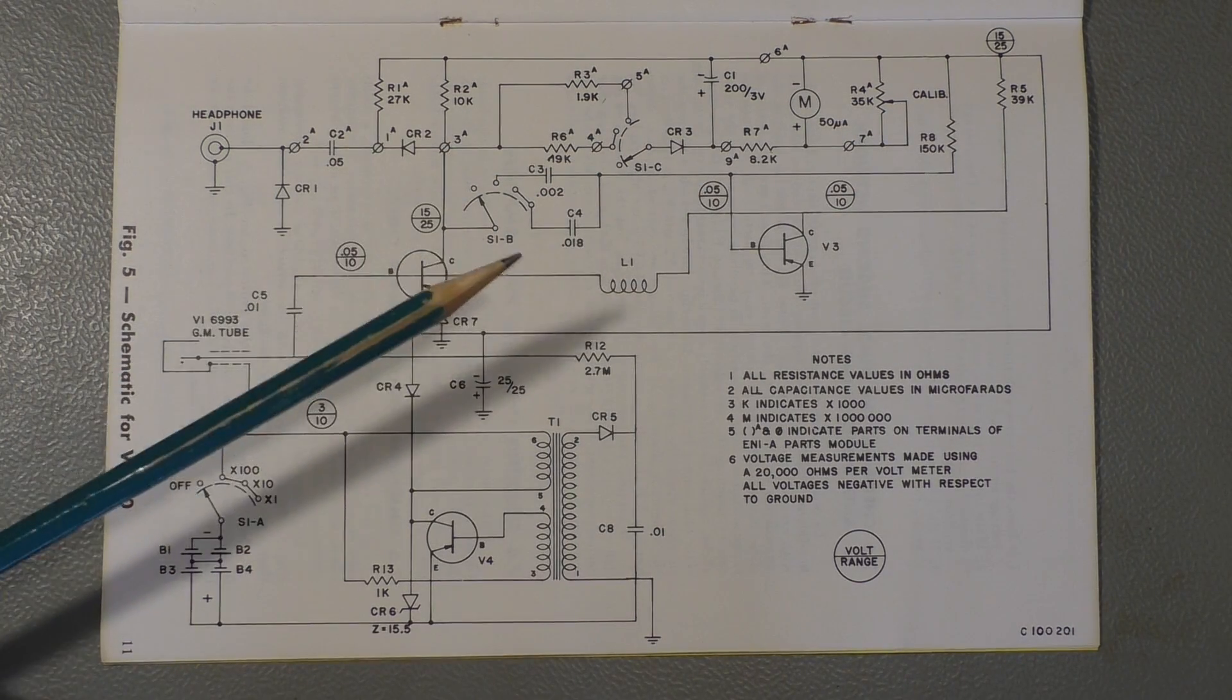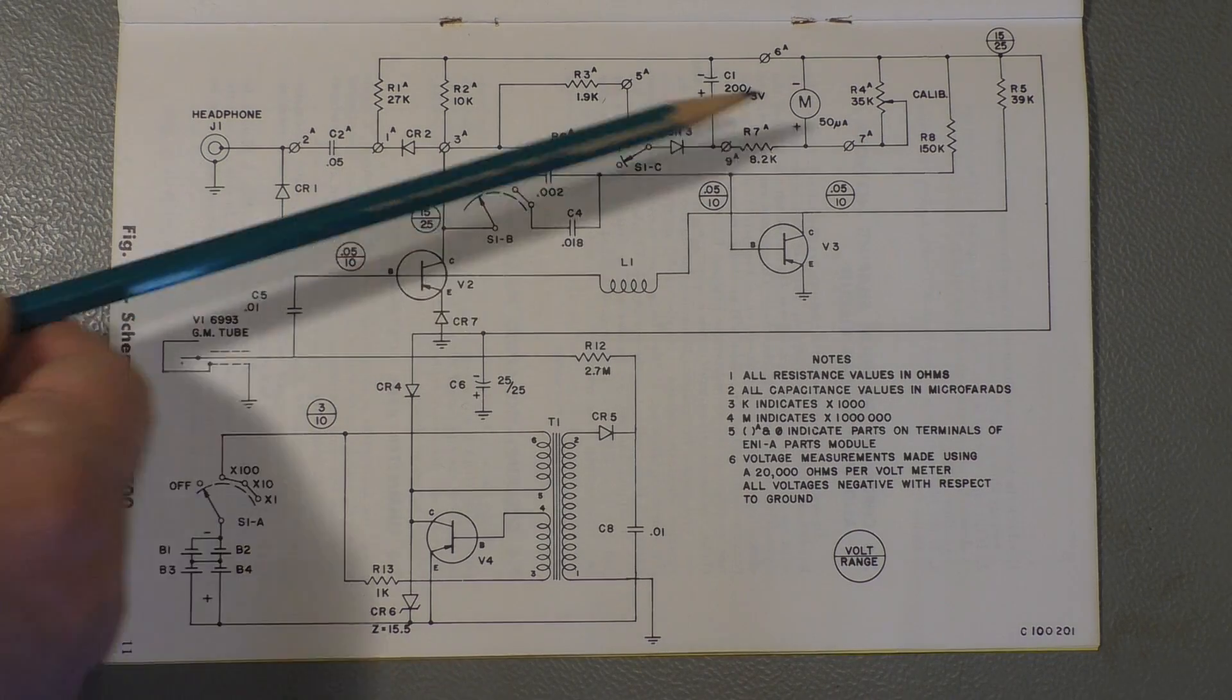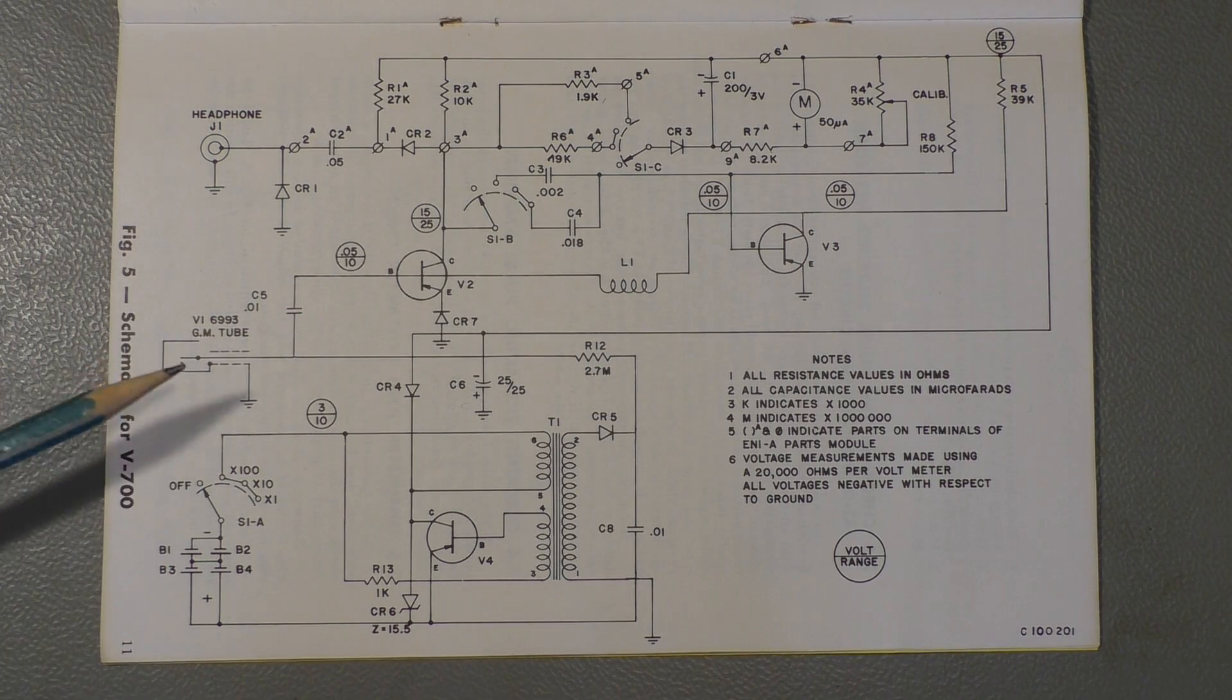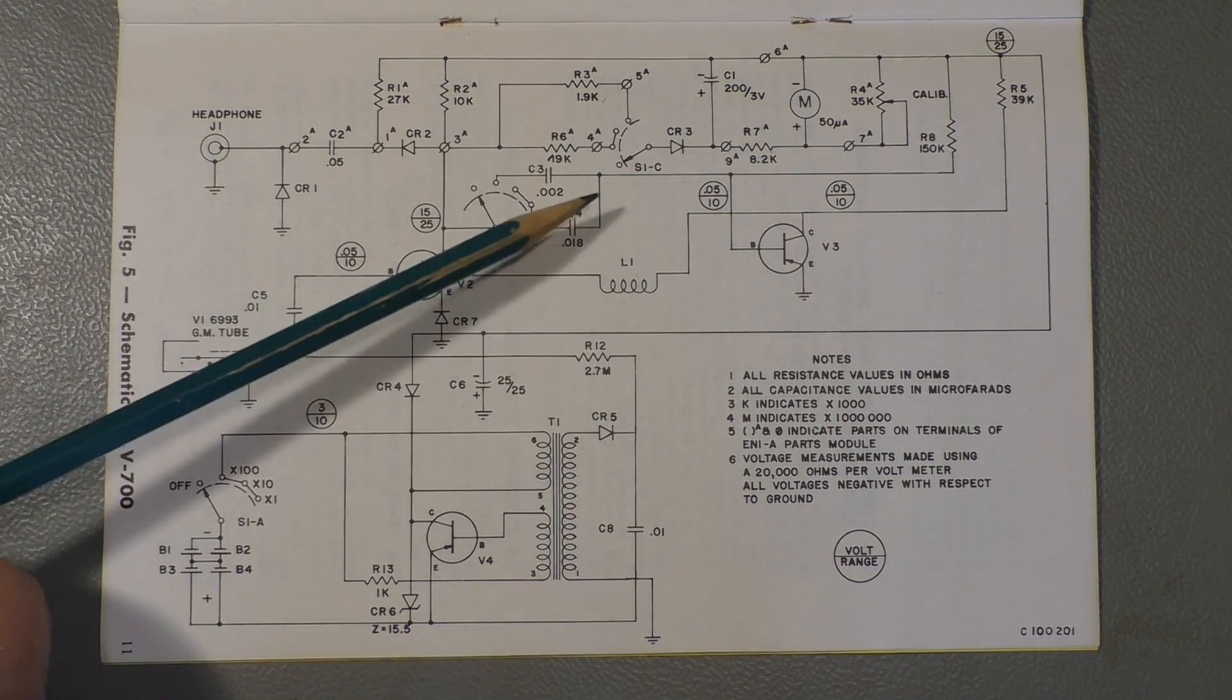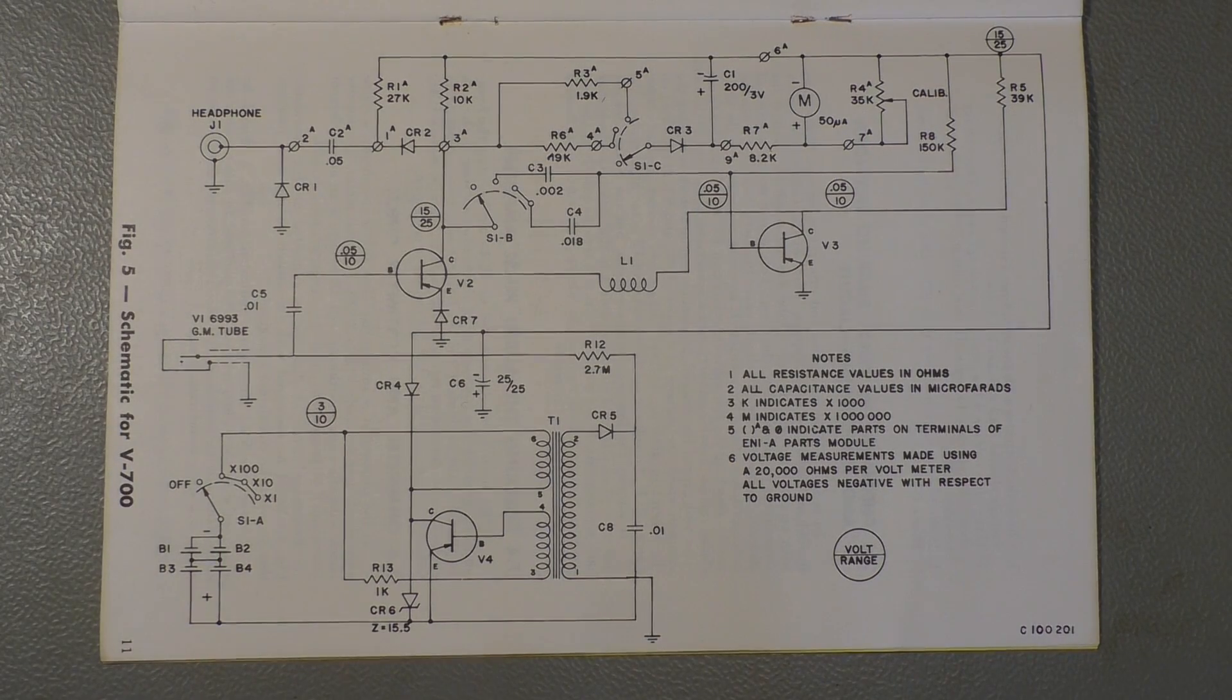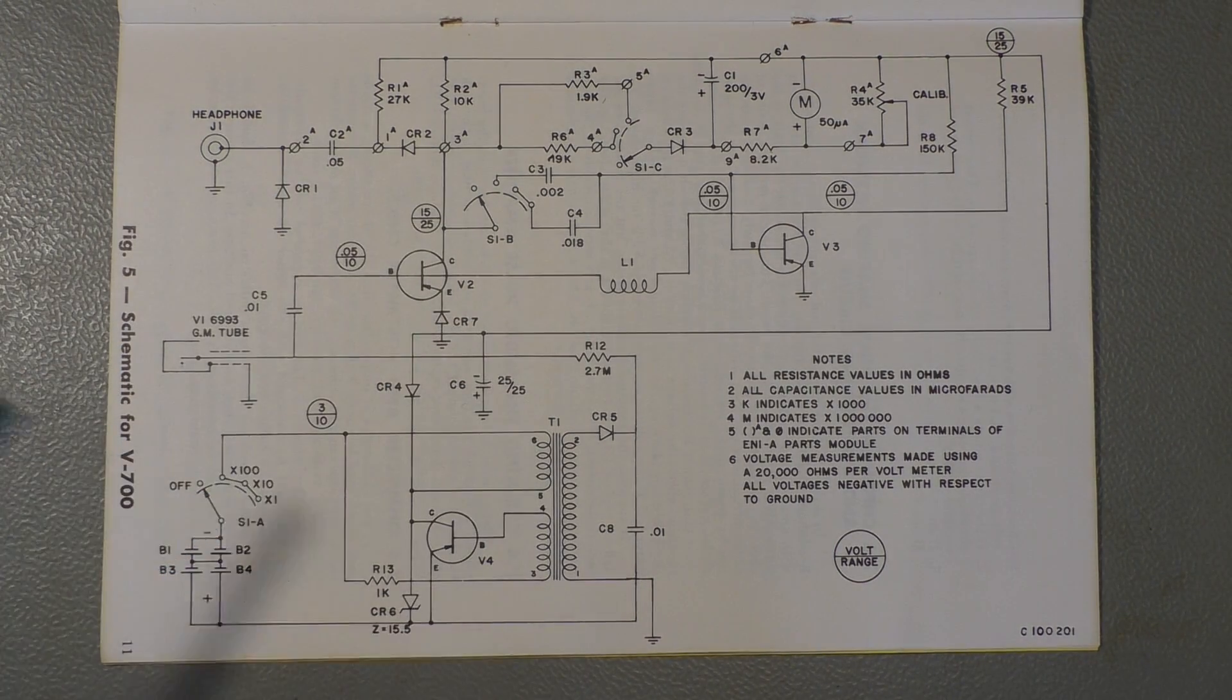And that means for every particle that comes here, makes an impulse, a bigger or a smaller impulse, it doesn't matter, it triggers this monoflop circuit for a short time. And, of course, the more impulses they come, the more impulses will be generated here until there are so many that they are so close together, that they almost touch each other. And then you have to switch from the X1 to the X10 or X100 range.